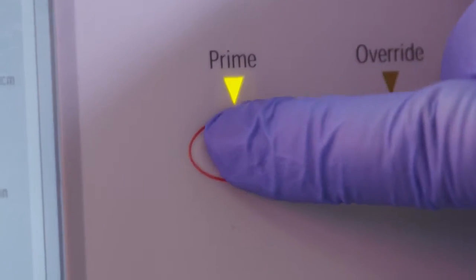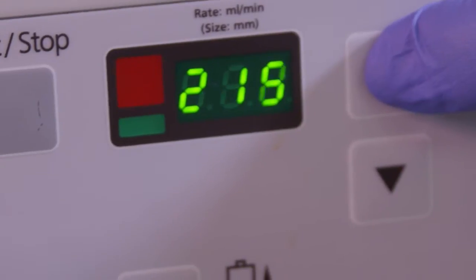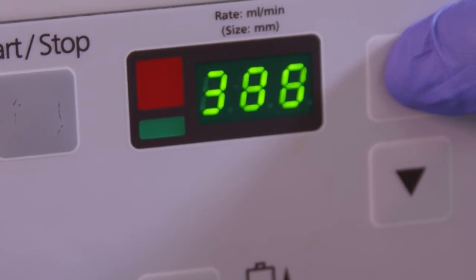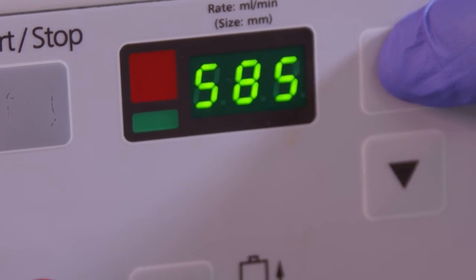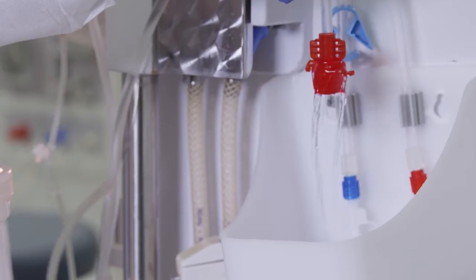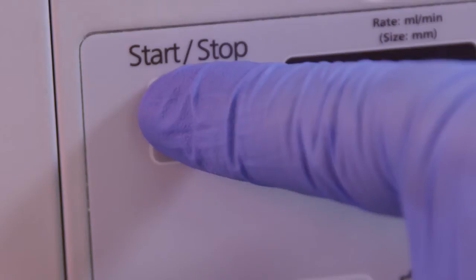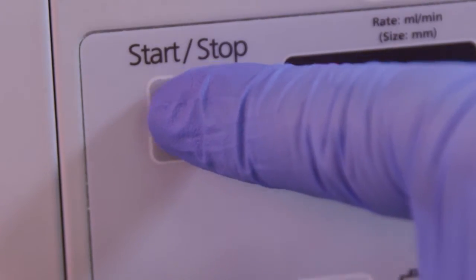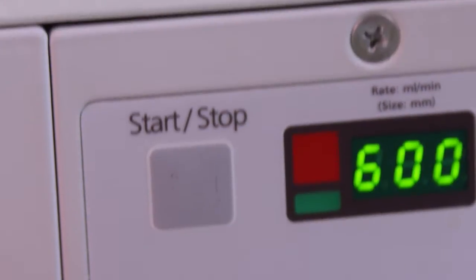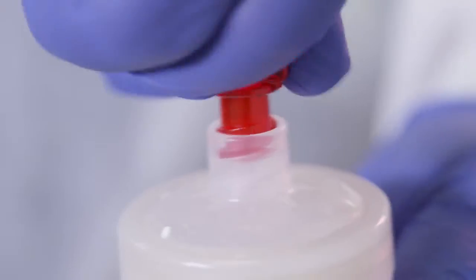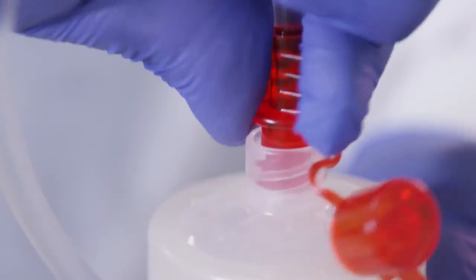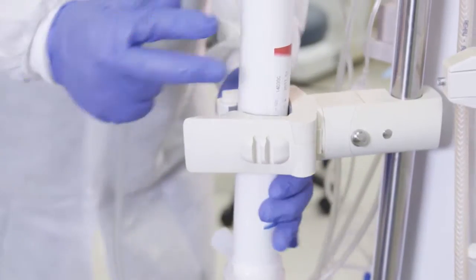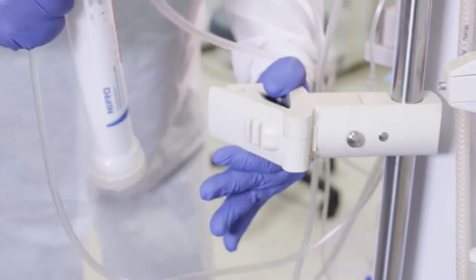Press prime. Turn blood pump to 600 milliliters per minute. And continue to prime the arterial blood line, ensuring all air is removed. After all air is purged, press prime to stop the pump. Connect the arterial line to the dialyzer. Rotate the dialyzer to venous end up and connect the venous line to the dialyzer.